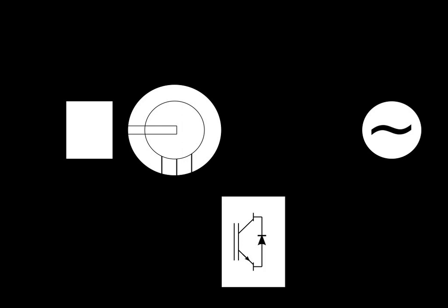In the schemes using a rectifier, the power flow was possible only out of the rotor because of the uncontrolled rectifier. Moreover, only sub-synchronous operation as a motor was possible. Another concept using static frequency converter had a cycloconverter connected between the rotor and the AC grid. The cycloconverter can feed power in both directions, and thus the machine can be run at both sub- and oversynchronous speeds.